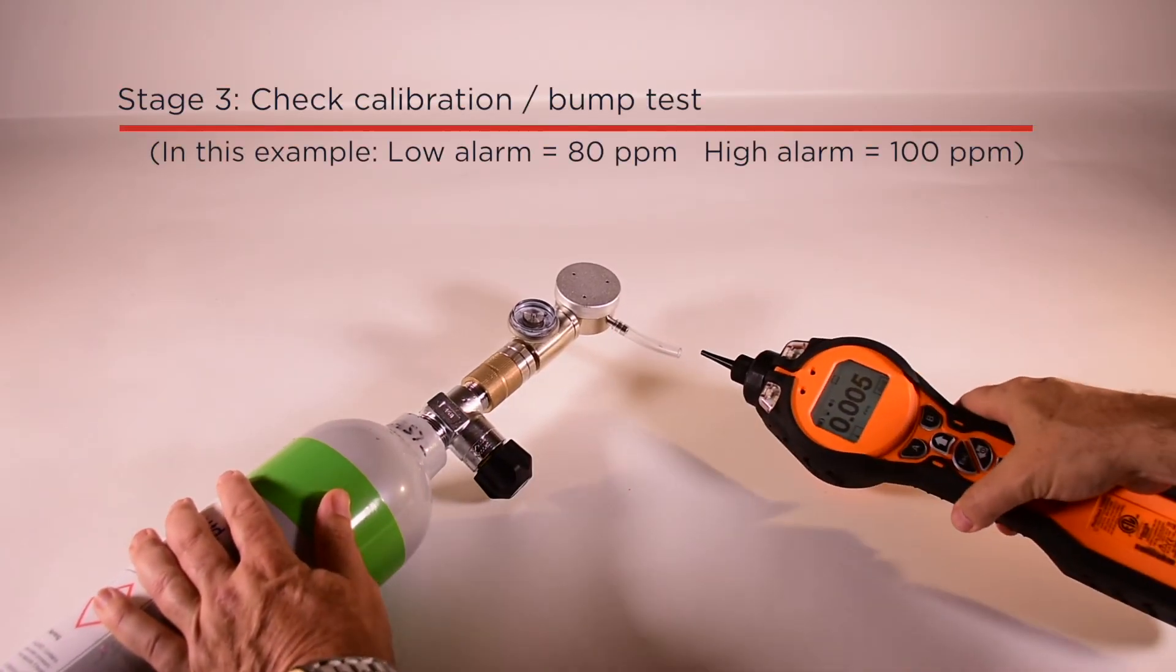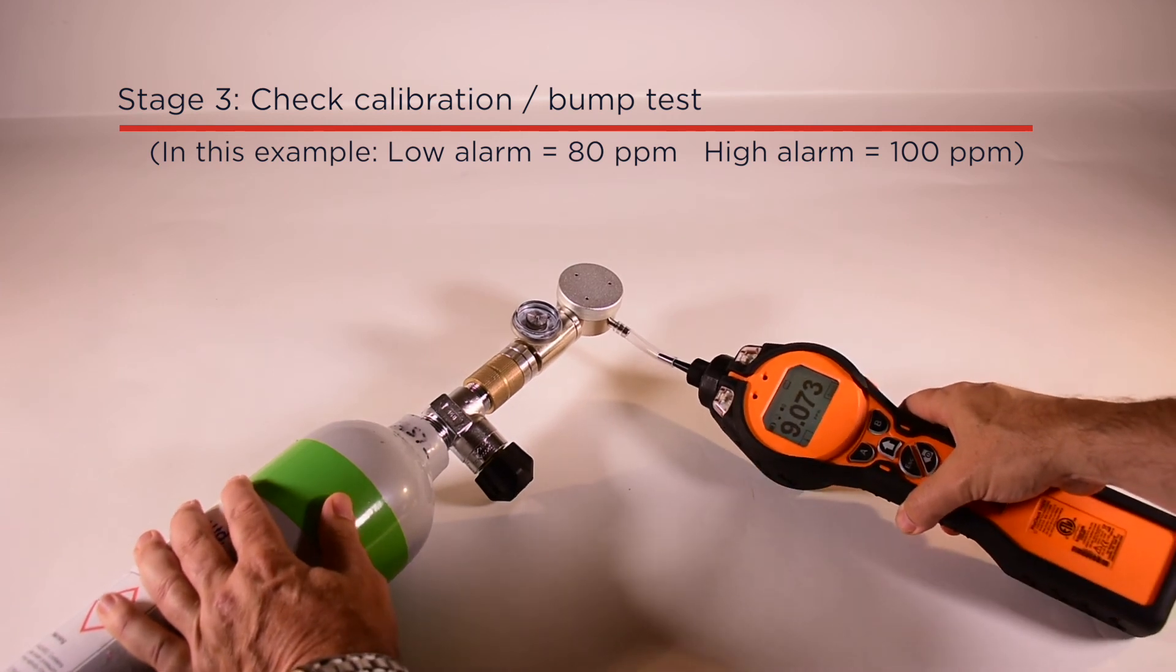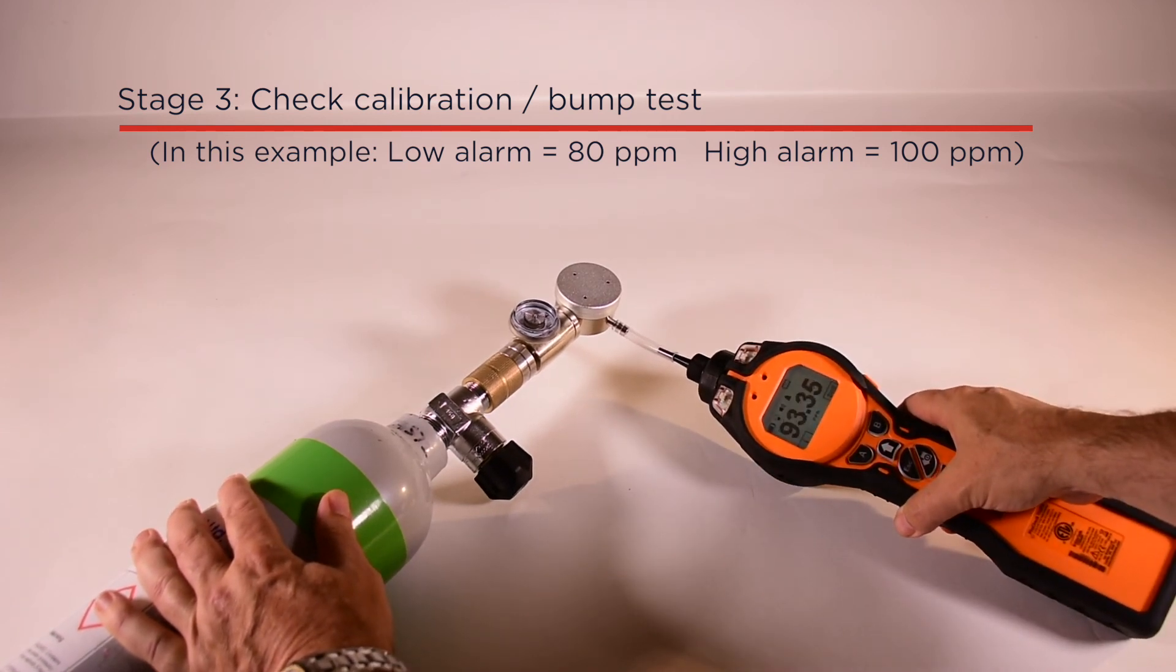Always bump test your TIGER instrument after calibration to ensure the reading and alarms are working correctly. In this example, the low alarm is set to 80 parts per million and the upper alarm to 100 parts per million.